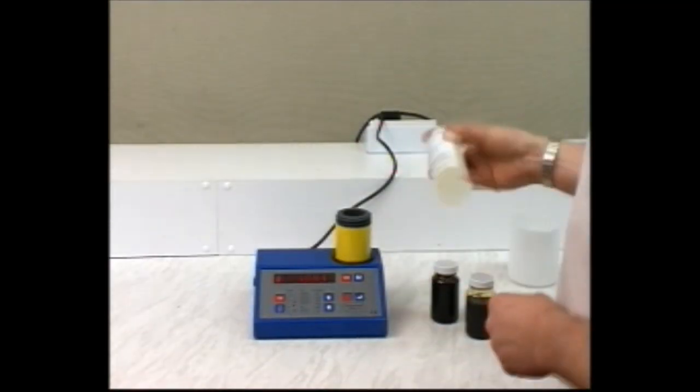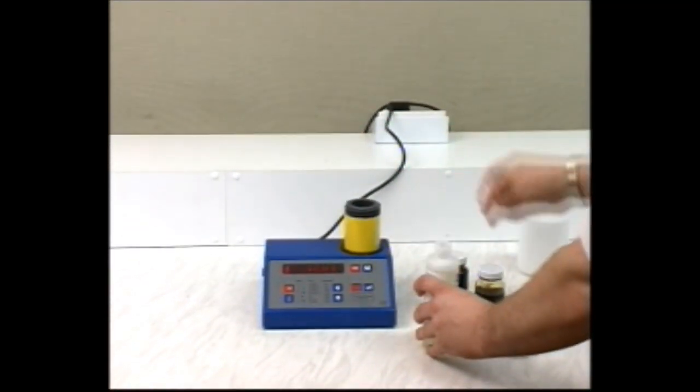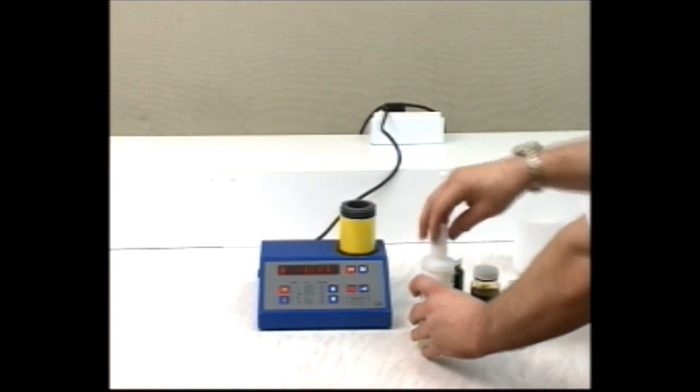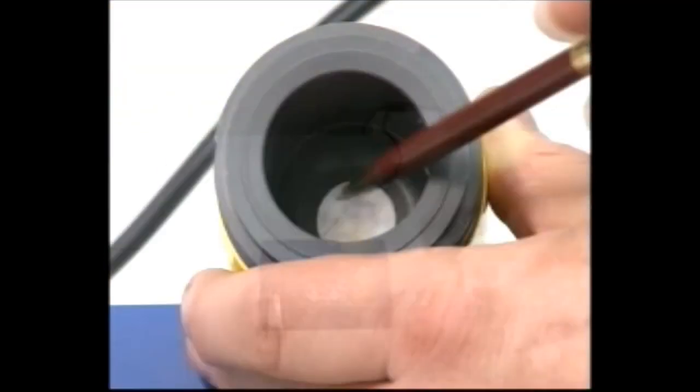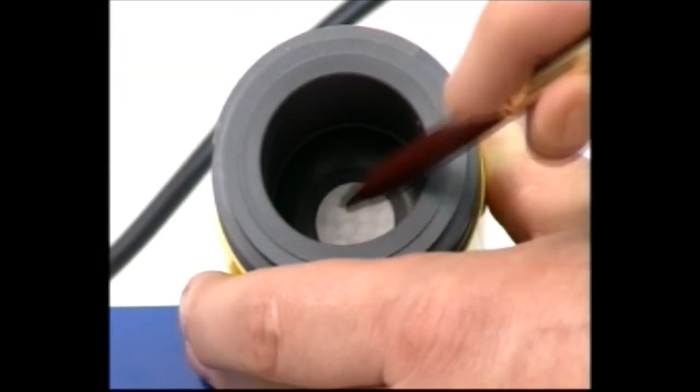Shake the reagent C bottle, attach the pourer spout, and fill the TBN cell with it up to the internal lip inside. Be careful not to damage the transducer.